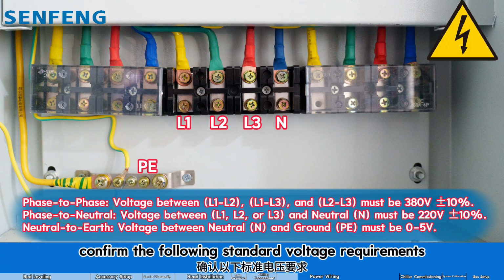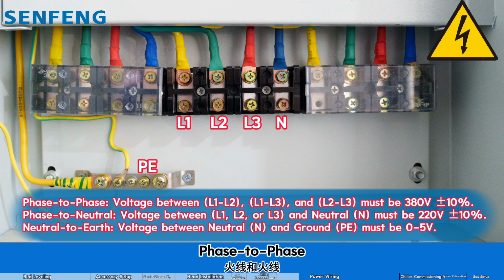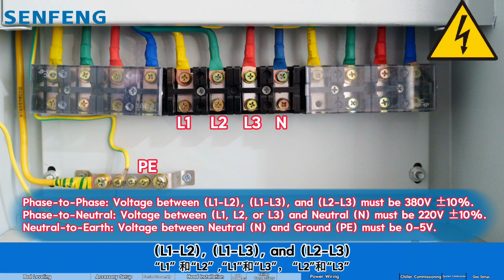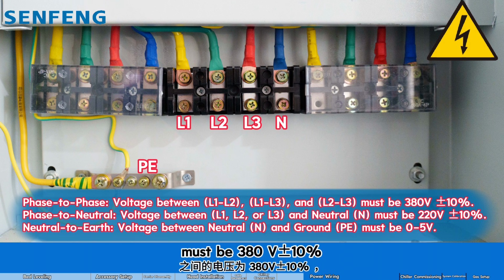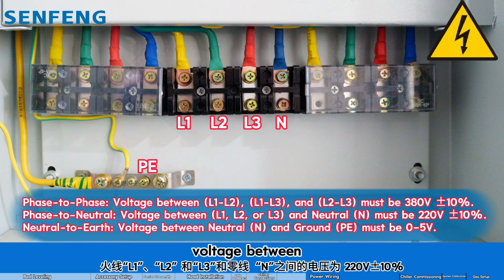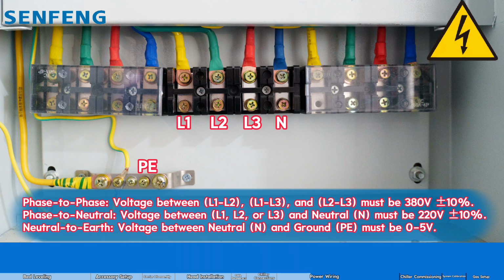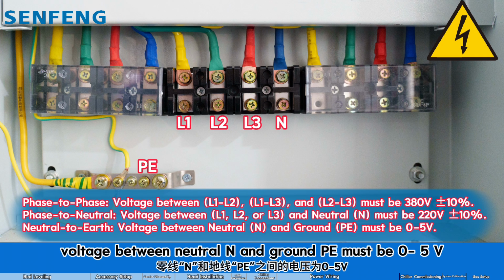Confirm the following standard voltage requirements. Phase to phase. Voltage between L1, L2, L1, L3, and L2, L3 must be 380 V plus or minus 10%. Phase to neutral. Voltage between L1, L2, or L3 and neutral, N, must be 220 V plus or minus 10%. Neutral to earth. Voltage between neutral, N, and ground, PE, must be between 0 and 5 volts.